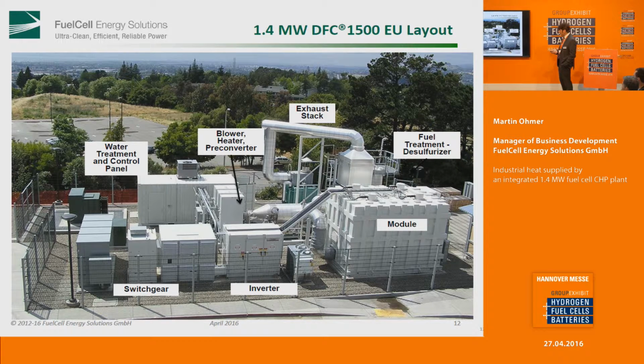Here we have a layout of a fuel cell plant in Connecticut. The module. Here the water treatment, control panel, the exhaust, fuel desulfurization, and the switchgear, inverters, and the electrical balance of plant. And this is 8 meters by roughly 13 meters. So it's relatively compact and silent. This is near a university, so we have no issues with noise, reduced noise level, because we don't have combustion inside. What's making the noise is coming basically from the inverter and some blowers.